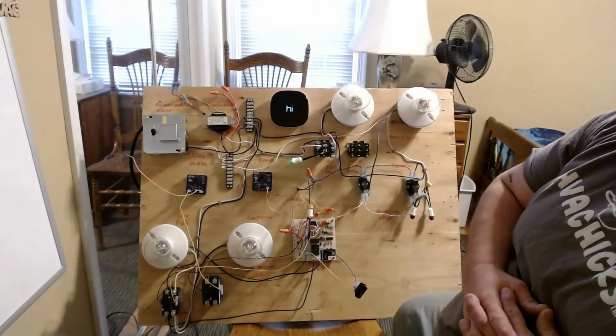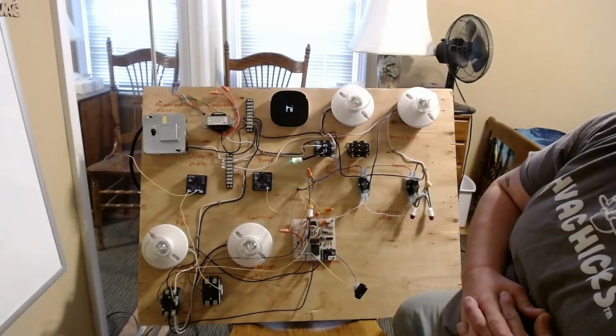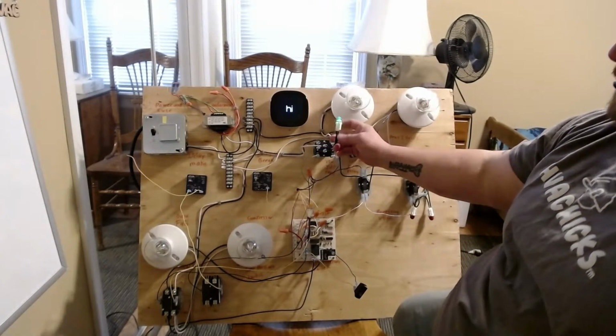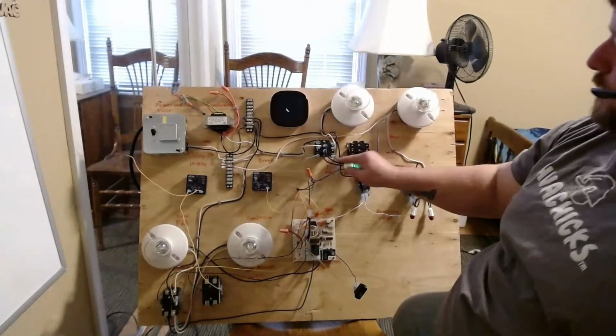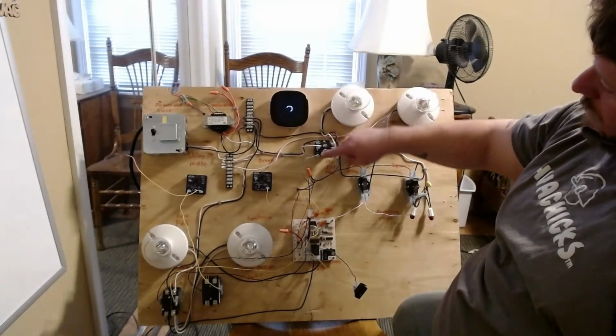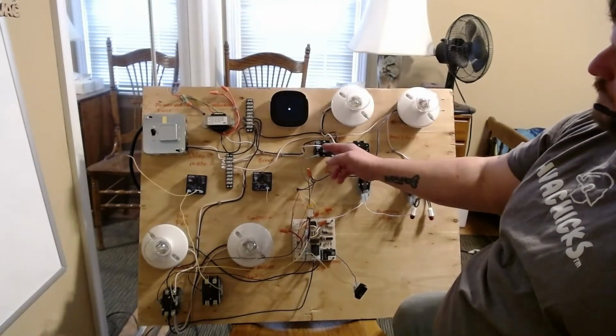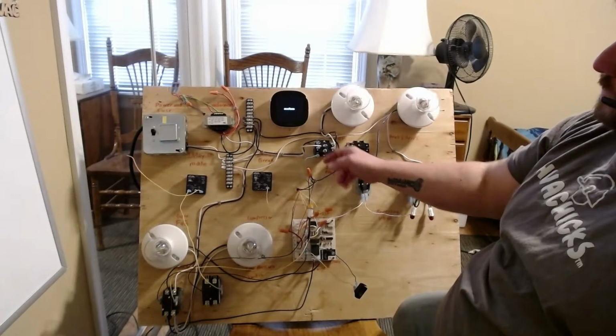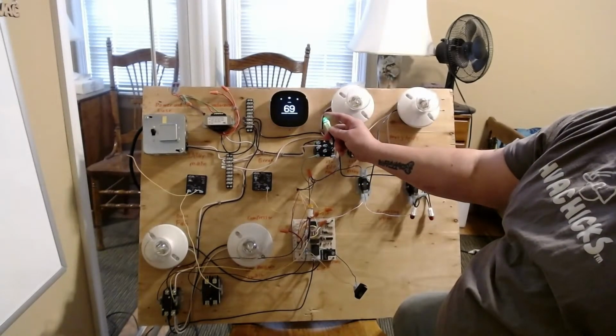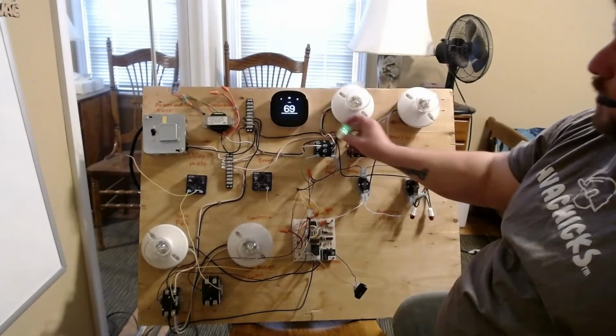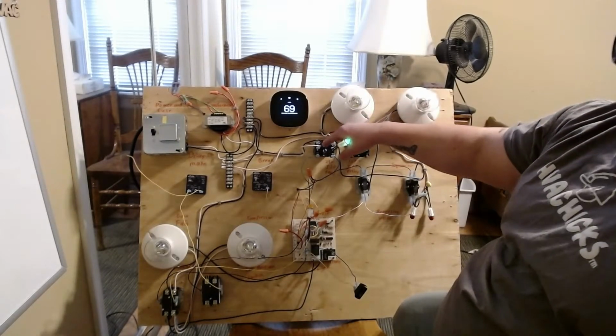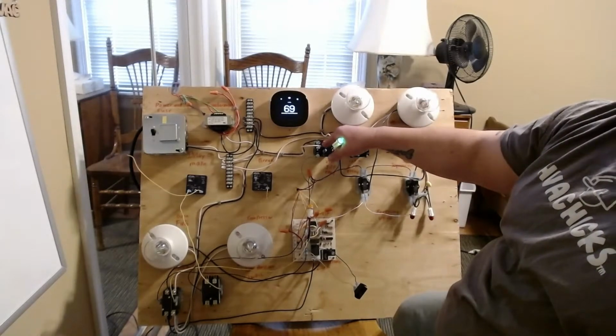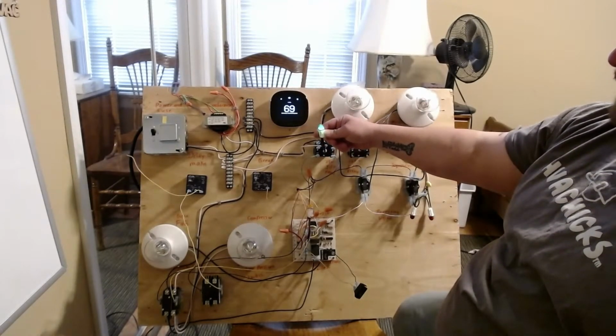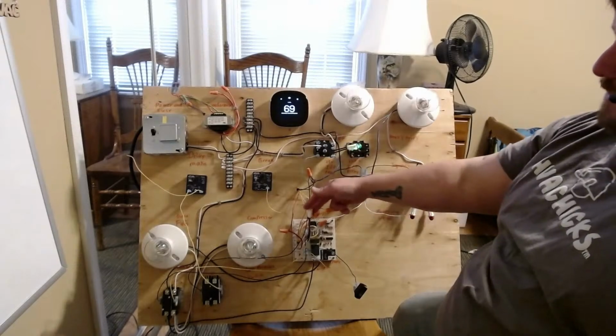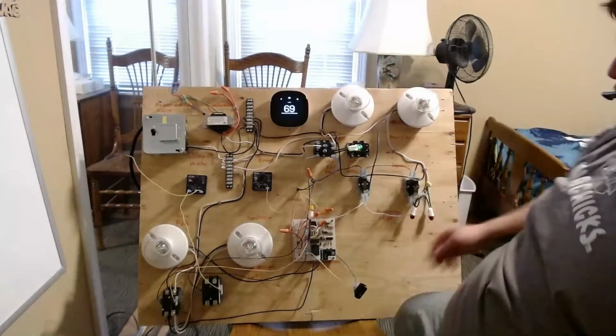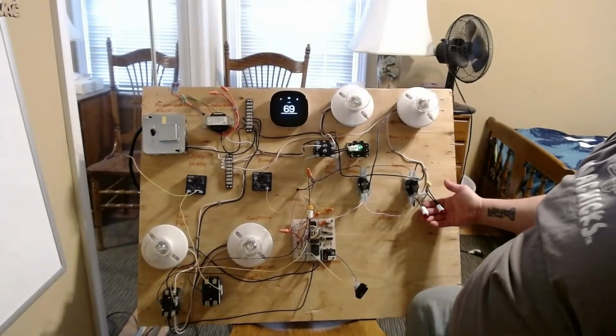It says hi. And yes, I have it hooked to the Wi-Fi so it can read the temperature and everything else. Now, if you see right here, this green light is lit. That is showing that on this relay, even though I don't have a call for G, my middle two terminals have line voltage. That's why this light is lit up. So you can see I have line voltage. Even when I don't have a call on these terminals, these center terminals are potentially hot and can hurt you. Hence the light. Now this is a 120 volt light. This one down here is a 24 volt light. These over here are 120 volt lights.